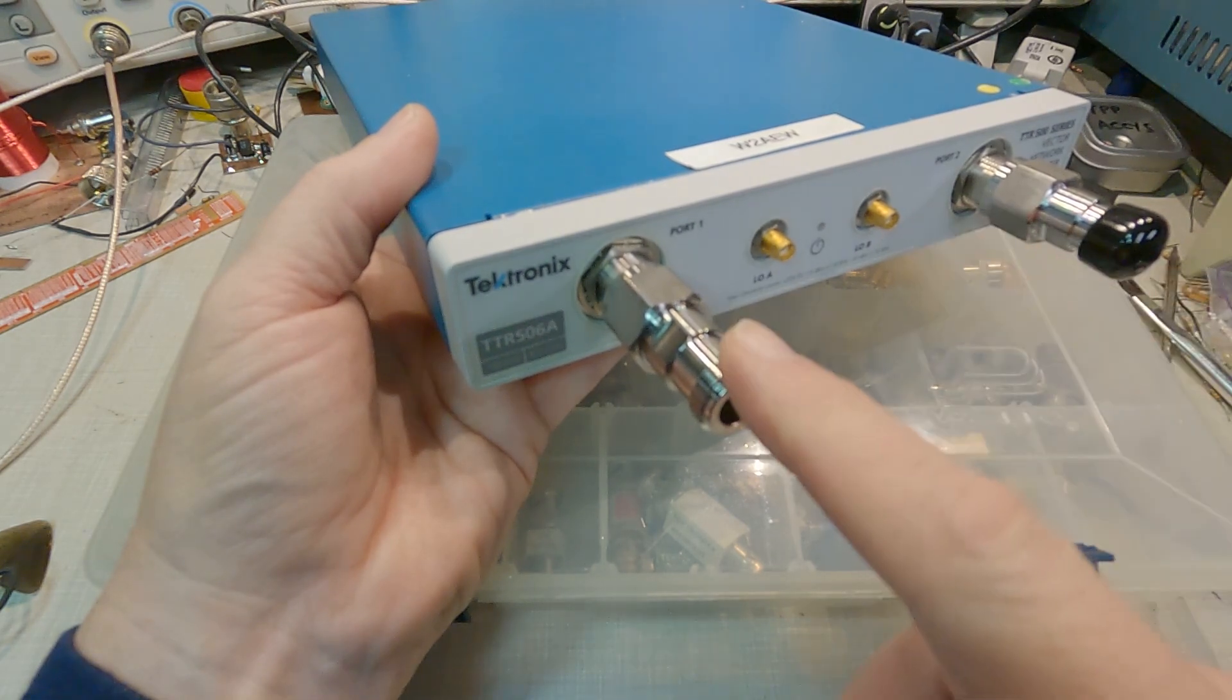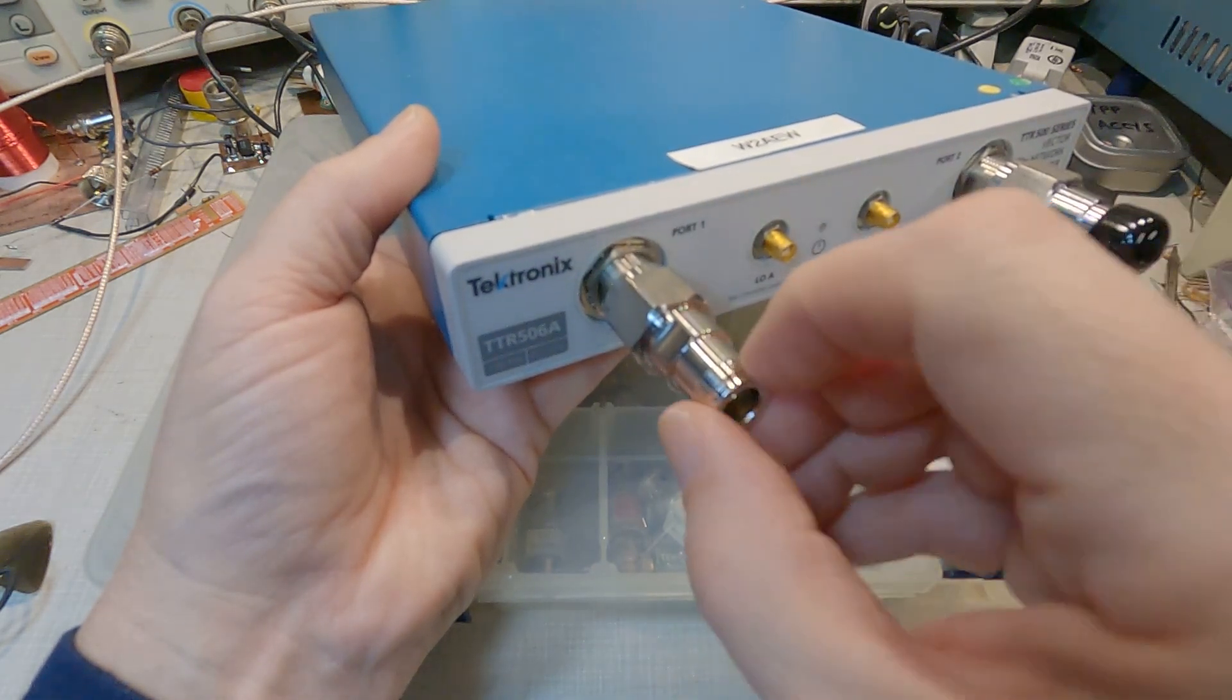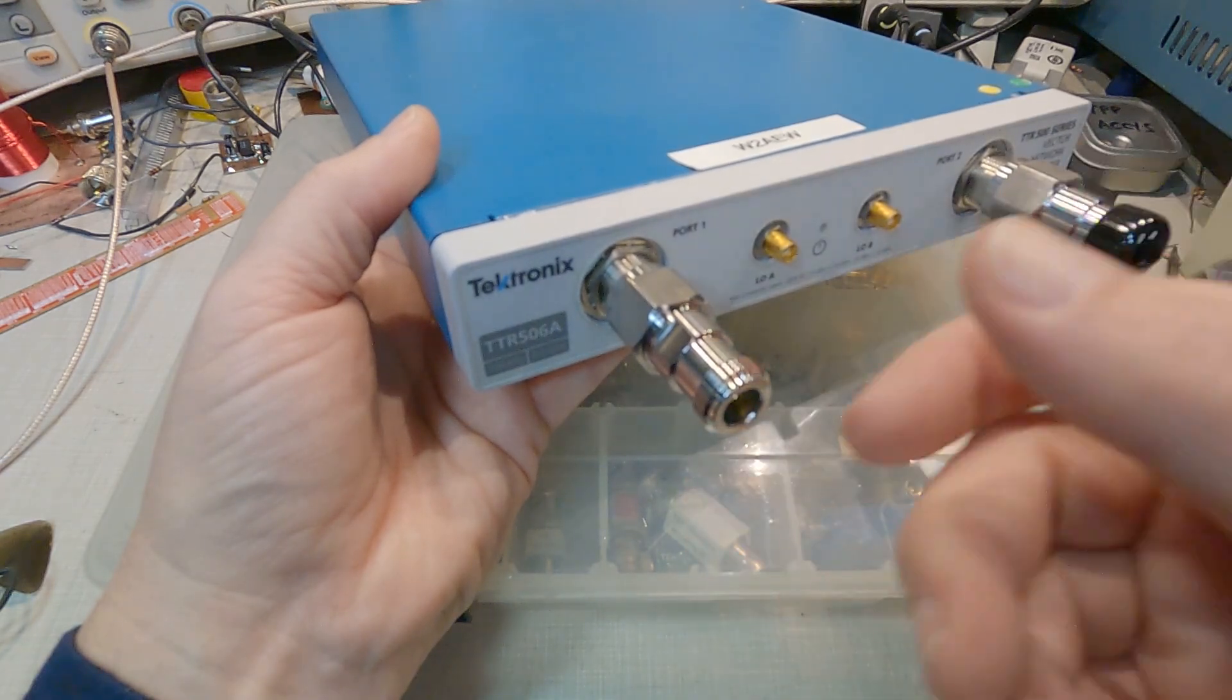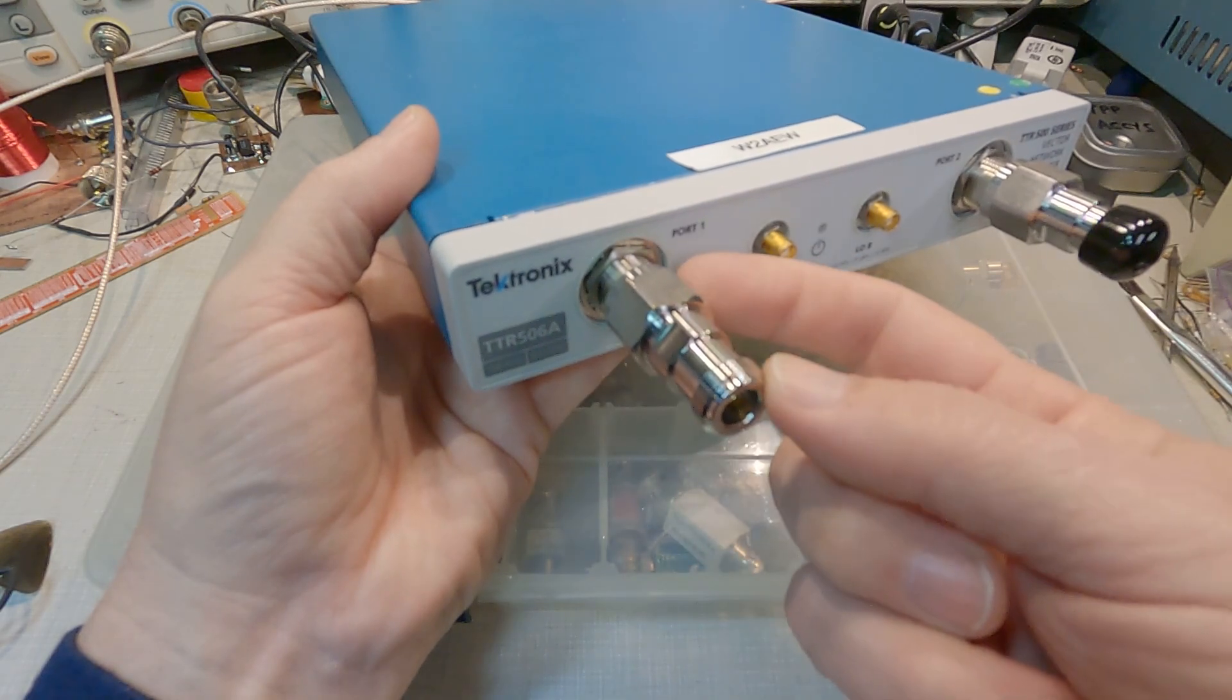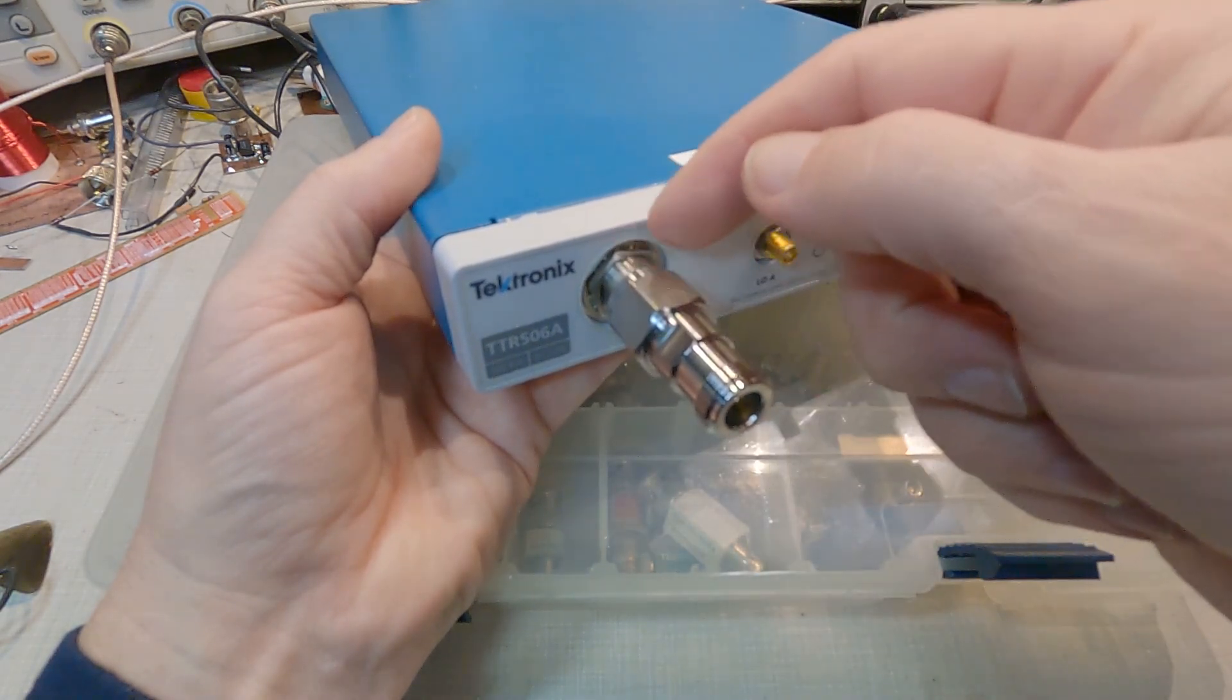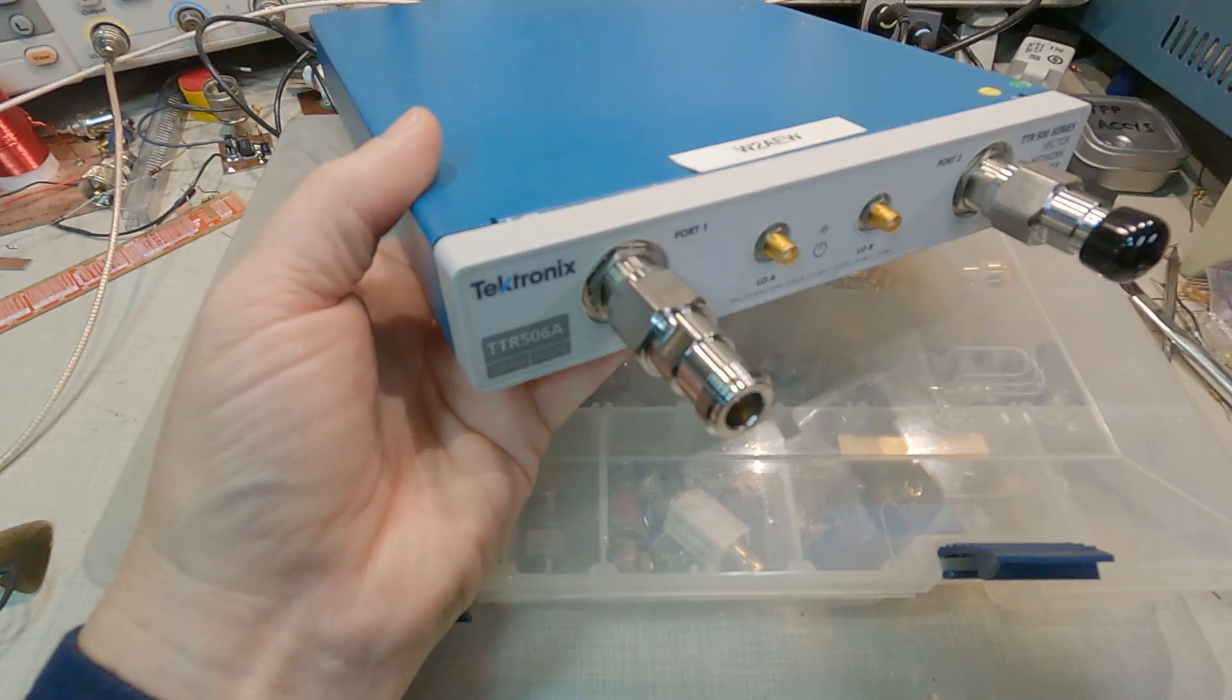so that if this gets damaged, bent, the threads get messed up, or even something gets banged into this, I can simply replace this relatively inexpensive connector saver and still preserve the nice pristine connector that's on the instrument itself.